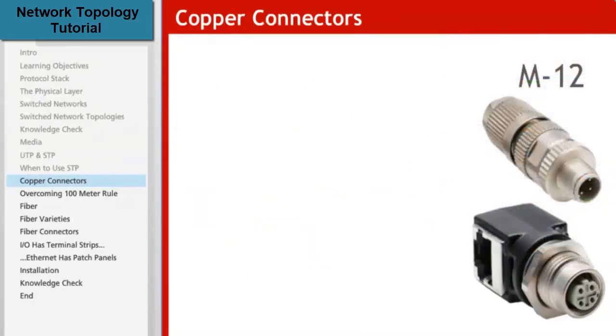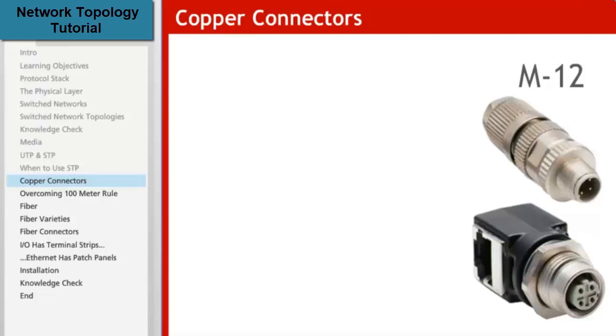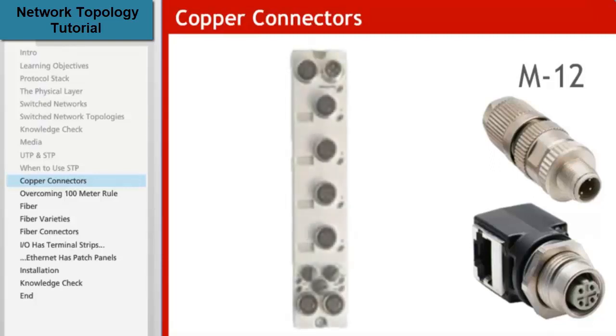M12 connectors are a much more rugged style connector that are appropriate for use on the plant floor. These 4 pin IP67 connectors are used with 2 pair or 4 conductor cables. They are commonly used with on-machine distributed I.O. products where the RJ45 connector is not appropriate.